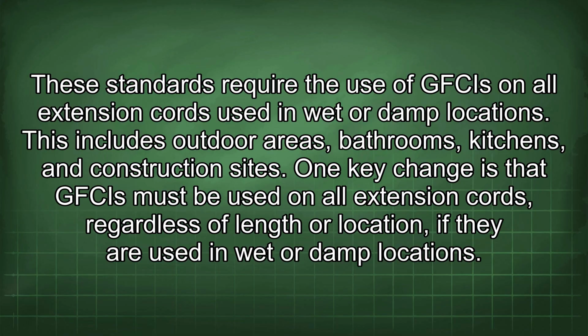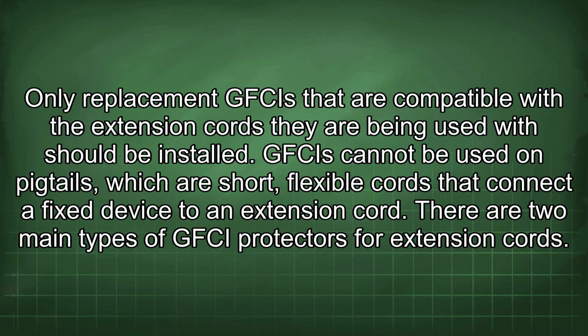This includes outdoor areas, bathrooms, kitchens, and construction sites. One key change is that GFCIs must be used on all extension cords, regardless of length or location, if they are used in wet or damp locations. Only replacement GFCIs that are compatible with the extension cords they are being used with should be installed. GFCIs cannot be used on pigtails, which are short, flexible cords that connect a fixed device to an extension cord.